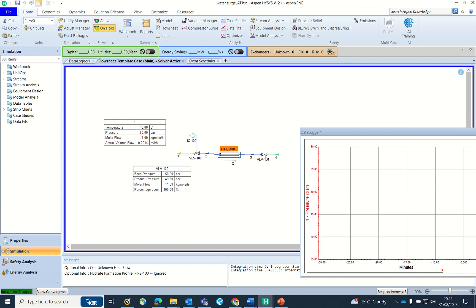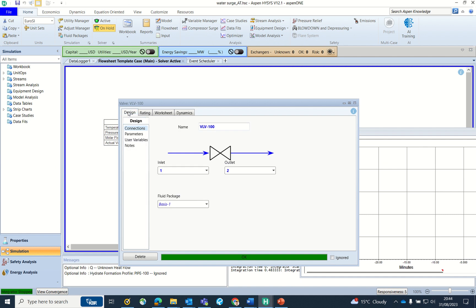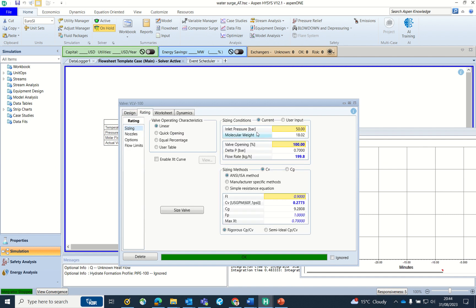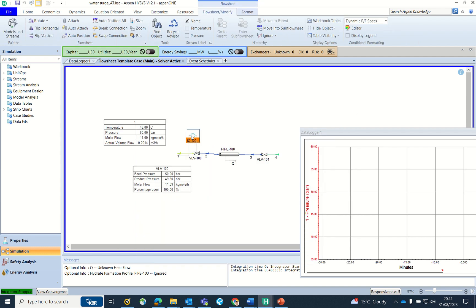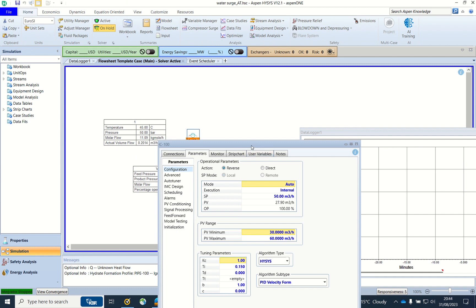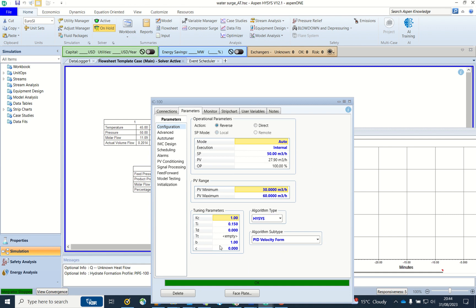There's an upstream valve and downstream valve, and they are control valves. For control valve sizing you have to see my previous video which talks about how to size a control valve. I have kept it linear and the CV is already sized at 100% open valve. I've also introduced one FIC which is controlling the flow rate at a set point of 50 meter cube per hour.